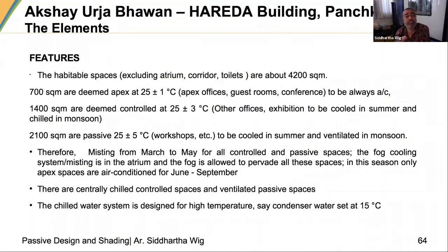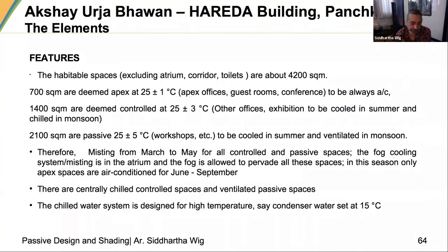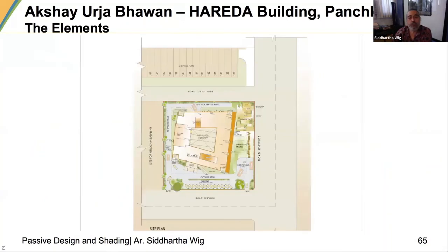This made our strategies much easier and more focused. We were looking at fogging inside the courtyard from March to May. There were centrally-chilled controlled spaces and ventilated passive spaces, so moving from a less conditioned to a more conditioned area would not cause thermal shock. We also designed the chilled water system to be set at a much higher temperature — 15°C was suggested. We looked at earth coupling for water but it turned out too expensive and we had to forgo it.